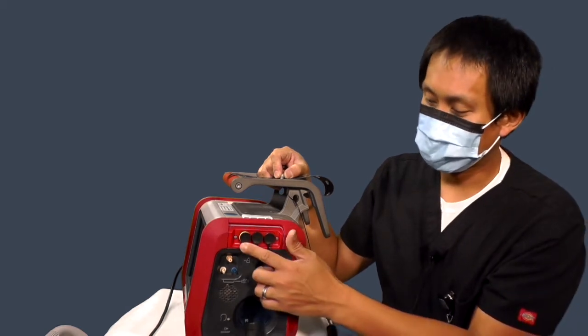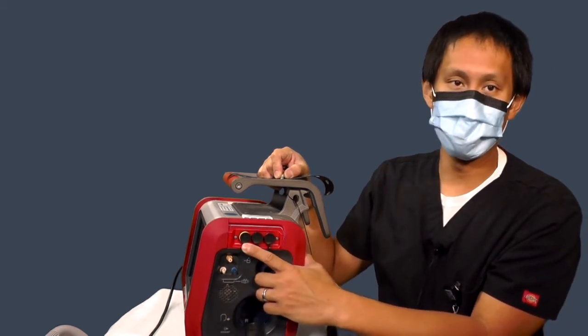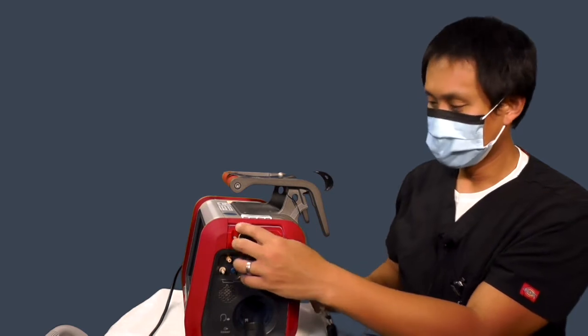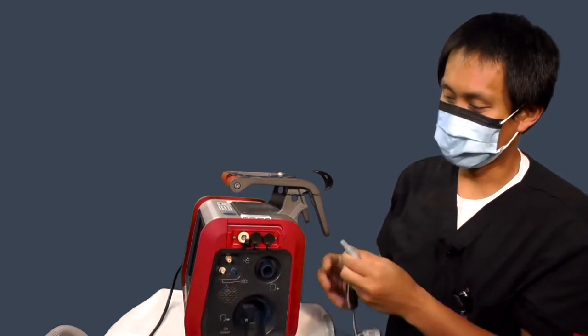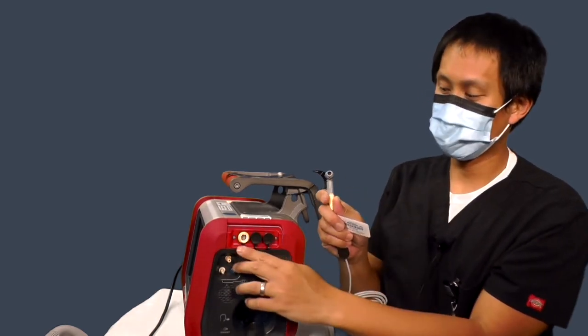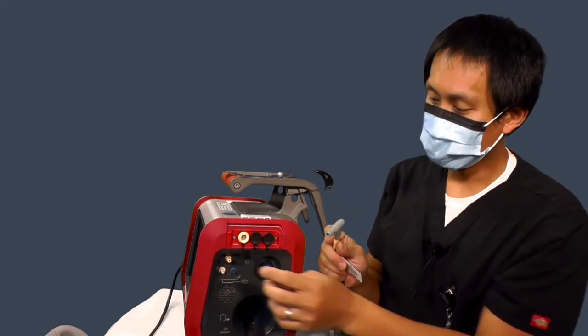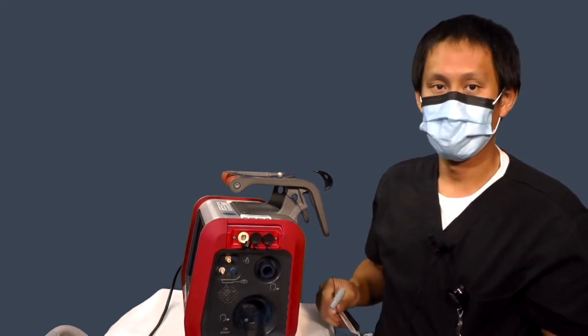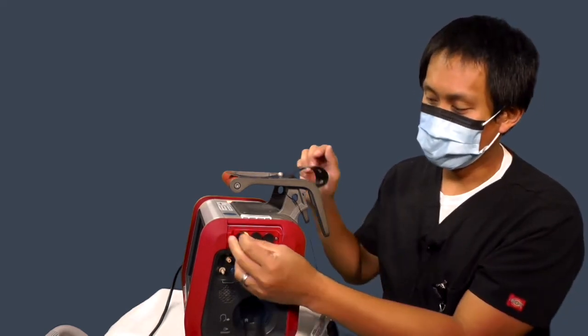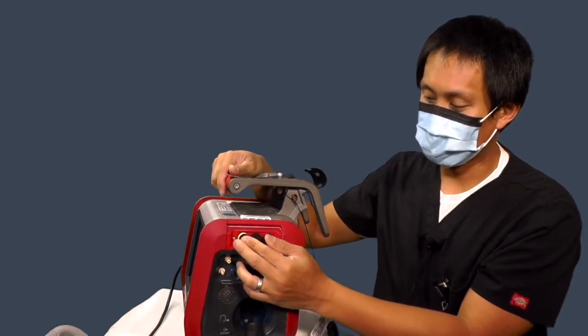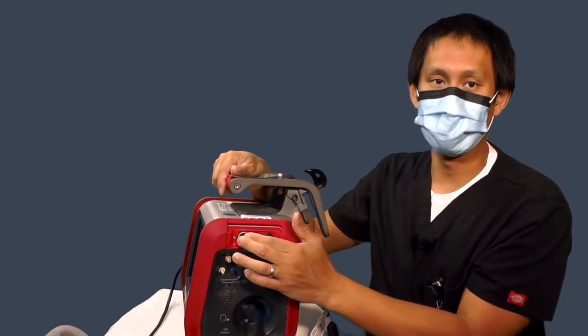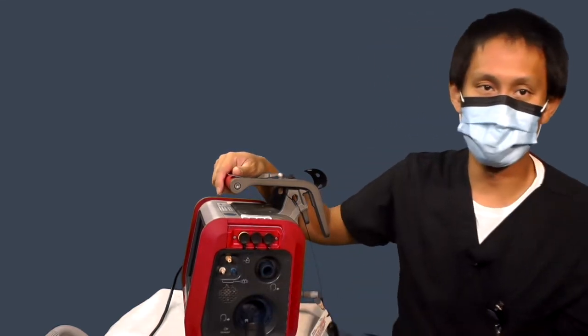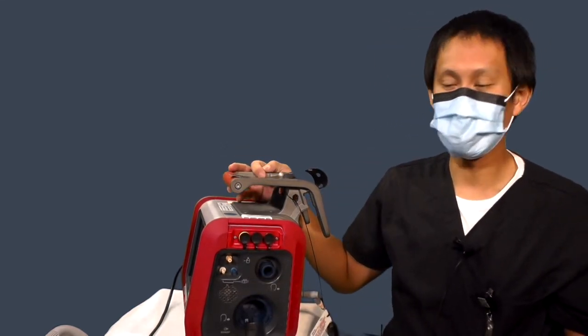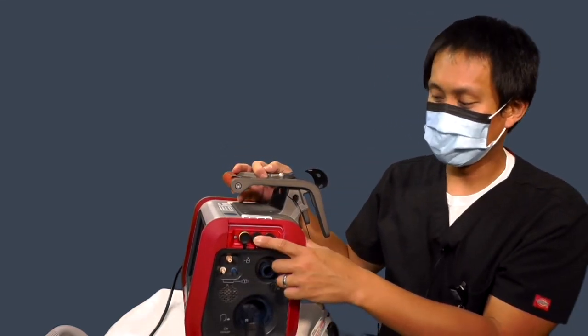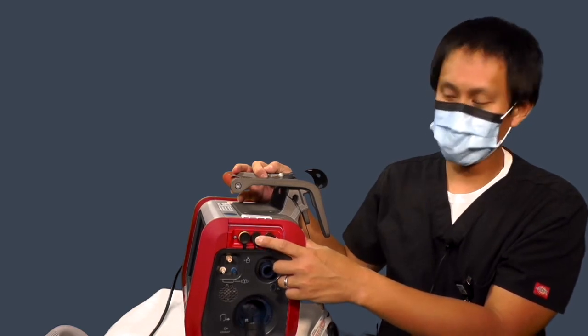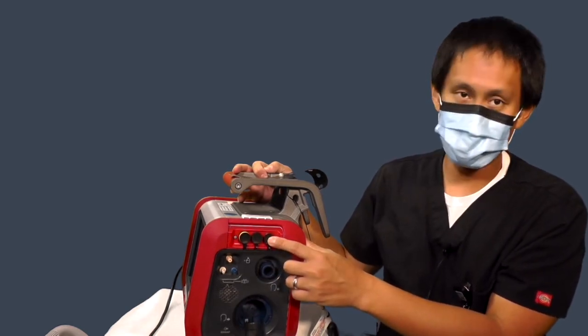So this ventilator has the capability of doing CO2, which is a plug port connector. If you do not have the CO2 capability on your transport vent, you may use your regular End-Tidal CO2 system that you're currently using. It does have the ability to slave to a monitor and to nurse call.